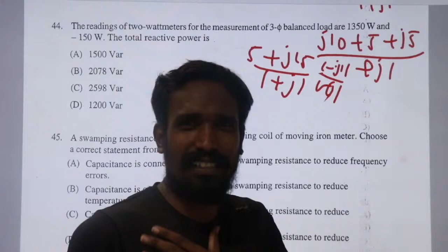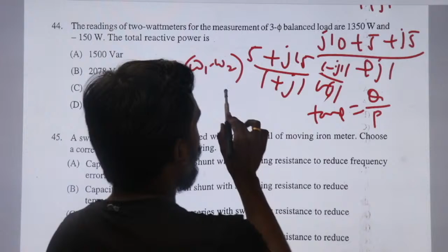They've given W1 and W2, find total reactive power. Many people make a mistake here. Reactive power as W1 minus W2 is 100% wrong. The correct answer is root 3 times W1 minus W2, because tan phi is reactive power by active power. Tan phi is opposite by adjacent, Q by P, reactive power by active power. Tan phi equals root 3 times W1 minus W2 by W1 plus W2, right?